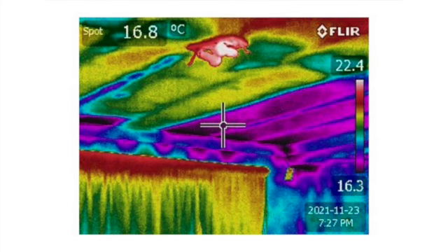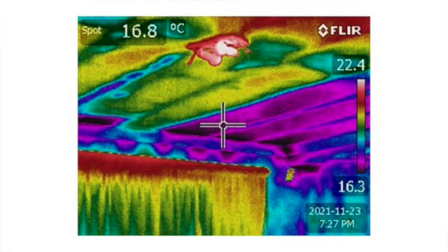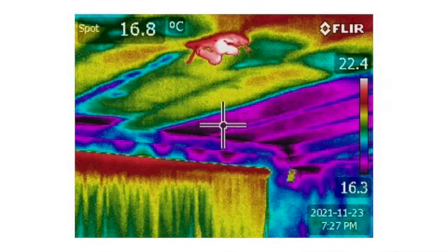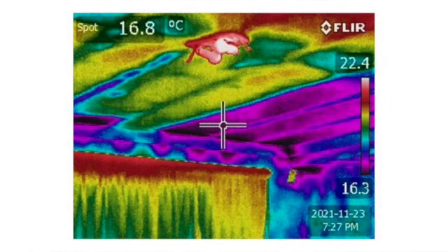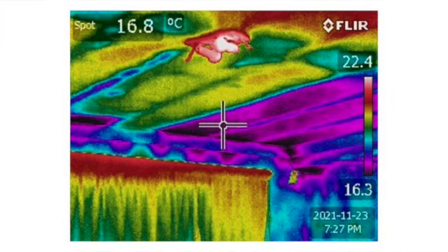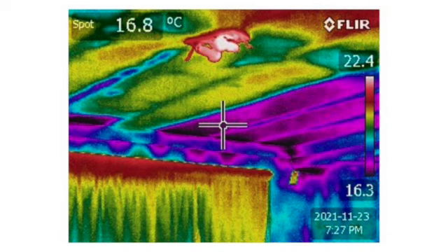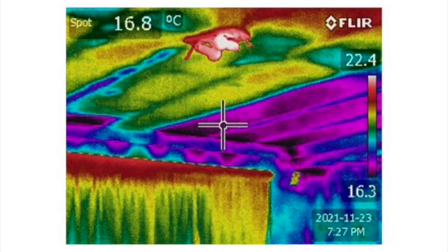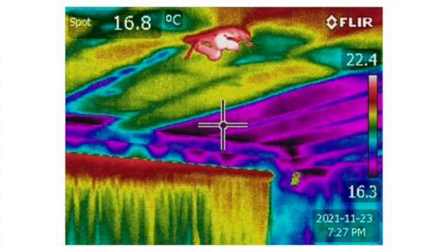The purple and black areas you can see on the ceiling show that the void between the ceiling and the flat roof was missing a lot of insulation. As already mentioned, warm air always travels to a colder area, and in this instance the cold purple part of the ceiling was so large and so cool it was clearly driving vigorous and chilling downdrafts, making the room very uncomfortable to sit in.